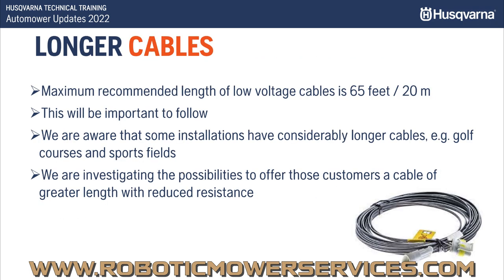Regarding longer cables: the maximum recommended length of low voltage cables is 65 feet, 20 meters. This is important to follow. We're aware some installations have considerably longer cables, e.g. golf courses and sports fields. We're investigating the possibility of offering those customers a cable of greater length with reduced resistance.